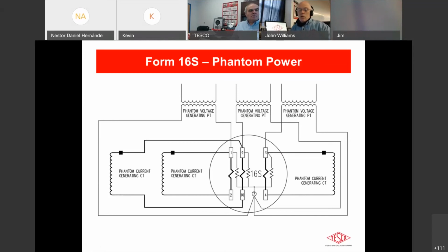The other thing that we can do when we're doing disconnect testing is you can still use the digital phantom current running through the meter while you're doing the disconnect test, so long as the current is synced in phase to the line current coming in off of the transformer, right? When we set up our disconnect testing, we read the phase off the line power coming into the unit with our metrology, and then we sync our current output to match it in phase, so that you can actually open and close that disconnect under real load.